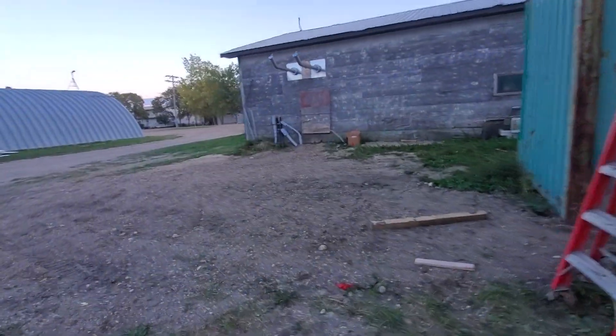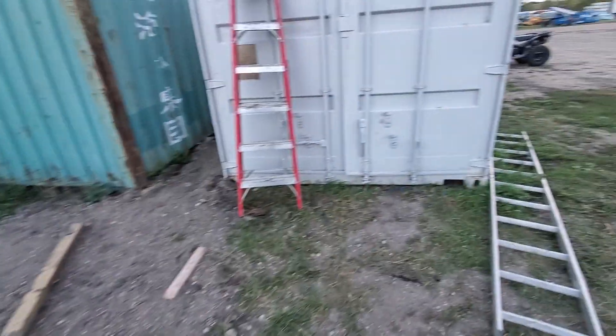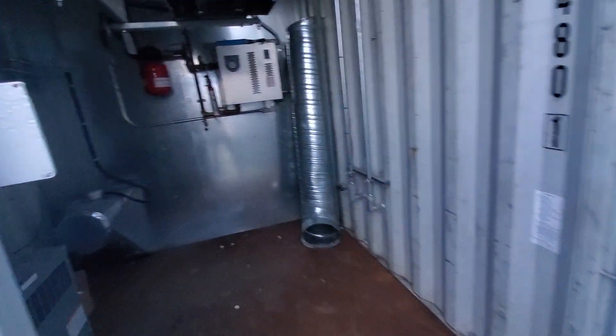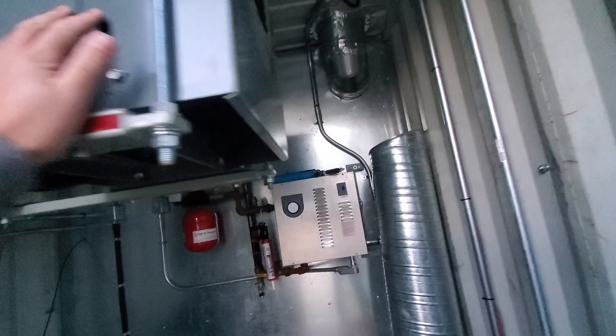Power comes in through those two wires, just going underground. In the back there's a utility room — no lights yet. There's a furnace and boiler from the old heating system, not operational. We have a transformer with power coming in and then running to the breakers: 30 amp breakers for all the 240 volt plugs and 20 amp breakers for the 110s.